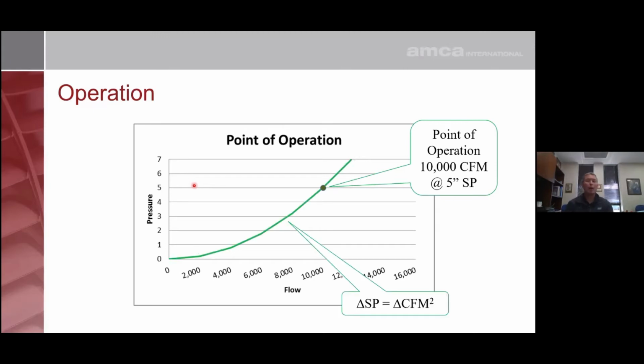Now, not everything follows a system law. There's certain pieces of equipment like cyclones and packed tower scrubbers that have a little bit different characteristic. But in general, systems operate in this manner, in that if you increase flow, pressure changes by the square of the change in flow. So if you double flow, pressure goes up 4 times, or 2 times 2 is 4. If you cut flow in half, pressure will be reduced to 1/4 of its original number. And this is a graphical depiction of how a system is going to operate.